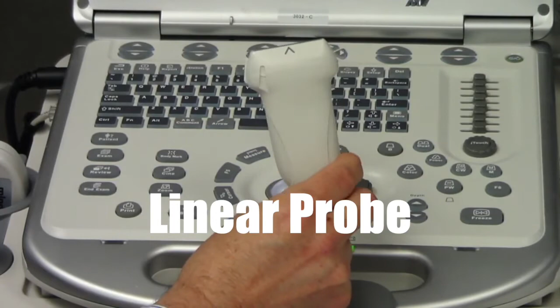And now we can start to see, if we go back to the machine itself, here is a picture of that linear probe. This linear probe is going to have multiple bandwidths through it, so it goes from 12 megahertz through a region of 4 megahertz. The highest number is usually to the left, and the lowest number is usually to the right. This means it has a broad bandwidth. You can see a probe marker, which typically on all the machines would be something a sonographer could feel in the dark. Remember, they're scanning in dark rooms many times, and you want to be able to feel the probe marker. It can sometimes have other things on the other side, which might be for probe guidance options. And we're going to have our overhead views as we pull down to our scanning here.